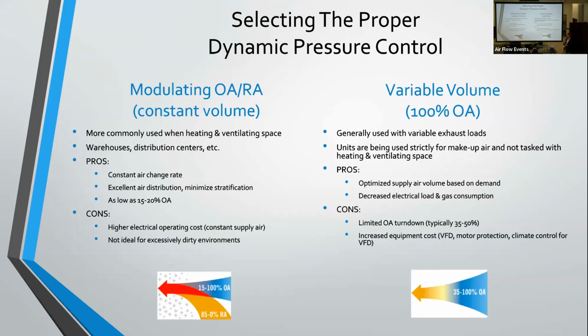Some advantages of outside air and return air units. One, you've got a constant air change rate being delivered to the space. So you've got consistent air distribution. You've got really good air distribution and minimal stratification because you're constantly turning that space over at a constant air change rate. Another advantage would be you can go down to as low as 15 to 20% outside air on return air units. Actually, we can go down to 15% outside air. Nobody else can, but 20% is obviously very low. So you're not burning a bunch of unnecessary fuel to heat unnecessary outside air that you're bringing into the space.